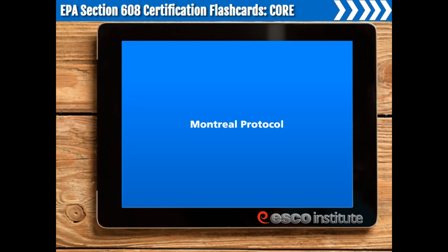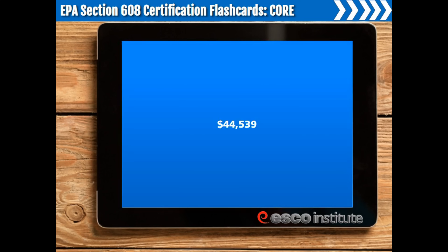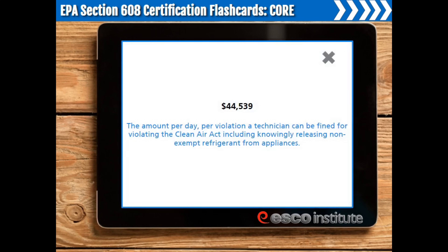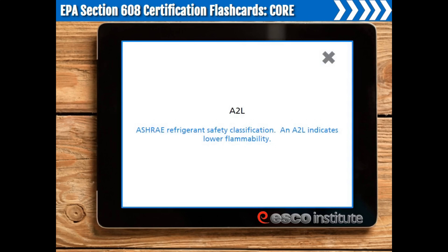Montreal Protocol. An international treaty that addresses ozone-depleting substances and their alternatives. $44,539. The amount per day, per violation, a technician can be fined for violating the Clean Air Act, including knowingly releasing non-exempt refrigerant from appliances. A-2L. ASHRAE Refrigerant Safety Classification. An A-2L indicates lower flammability.